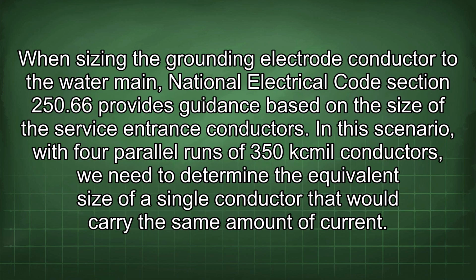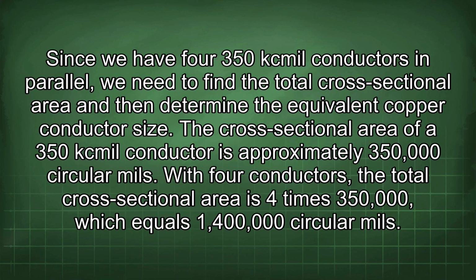When sizing the grounding electrode conductor to the water main, National Electrical Code Section 250.66 provides guidance based on the size of the service entrance conductors. In this scenario, with 4 parallel runs of 350 kcmil conductors, we need to determine the equivalent size of a single conductor that would carry the same amount of current. Since we have 4 350 kcmil conductors in parallel, we need to find the total cross-sectional area and then determine the equivalent copper conductor size.